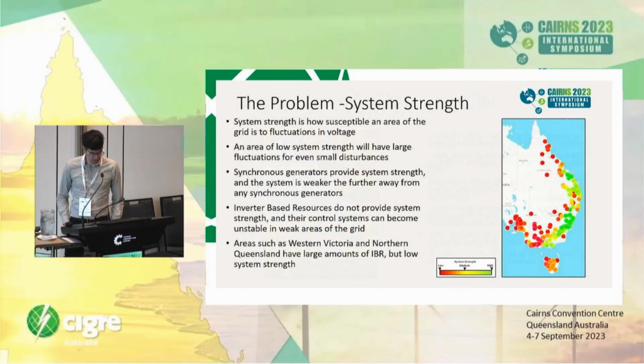The other problem, another massive problem that we're starting to see, is system strength issues. System strength is really how susceptible the grid is to fluctuations in voltage. It's particularly an area of concern in areas with high levels of IBR, inverter-based resources, because in those low system strength areas, they can become unstable. Synchronous generators provide system strength services and help stabilise the grid, but again, as they retire, we get more inverter-based resources and the overall grid strength becomes weaker. And of course, inverter-based devices, as they are currently, do not provide some of these system strength services. We have a lot of very weak areas of the grid, in particular far north Queensland, where we are now, and in the south, down in Western Victoria and parts of South Australia, very, very weak systems.